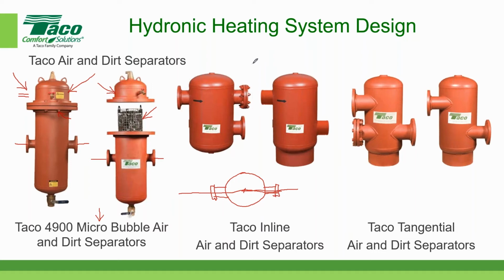The only difference, so there's a couple of differences. The one on the left is a flange connection. The one on the right is a grooved pipe connection, which would be similar to Victaulic. And the one on the left also has an auxiliary strainer in here. You can get those strainers for the Victaulic too, but I wanted to show that you can get them in both different ways. And then the third category of air and dirt separators is called a tangential.